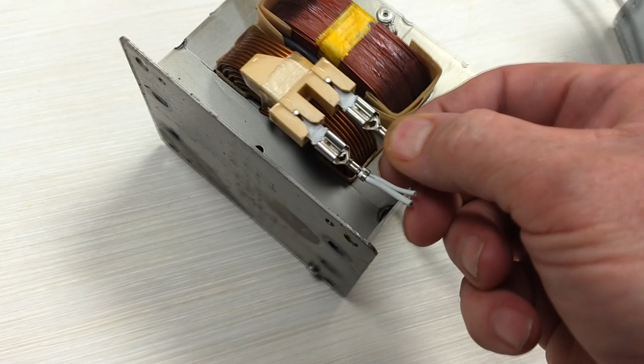Now, the one I'm touching with my thumb is the high voltage winding, and you can see the end of that winding is connected to the frame of the transformer. That means all the metal of this transformer is at high voltage potential when in operation. So that's a hazard you have to be aware of. Never touch it. And here's the other end of the high voltage winding, this tab here.